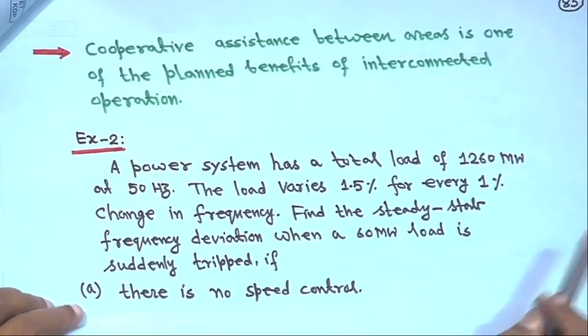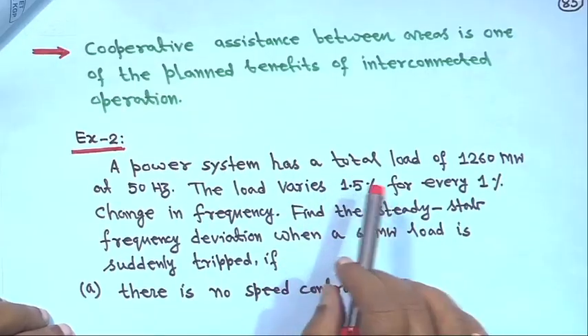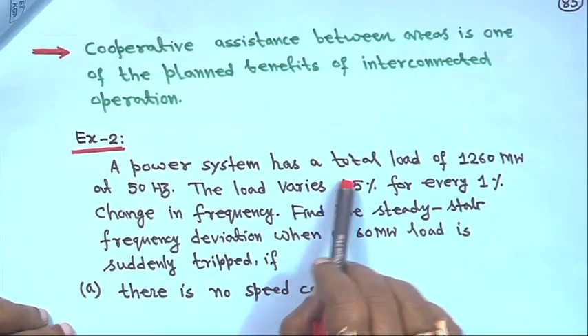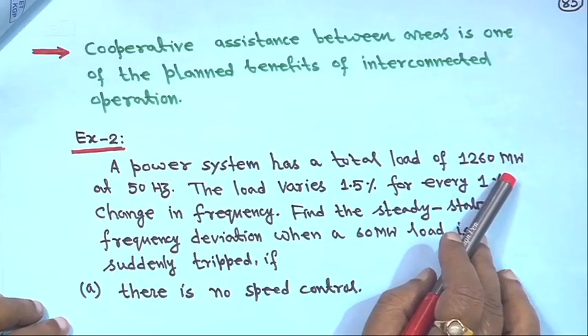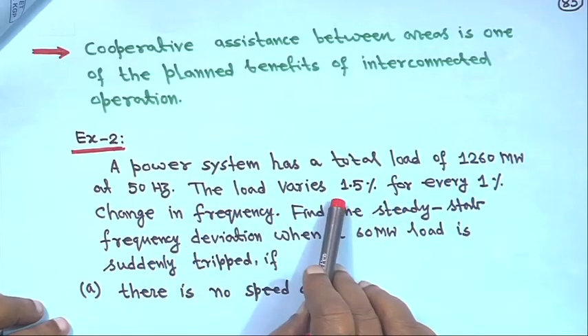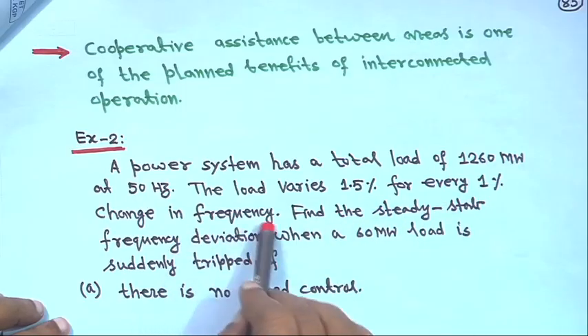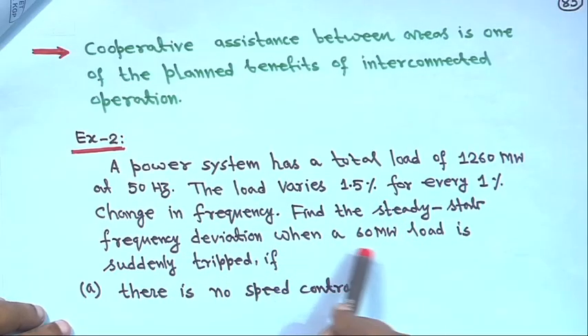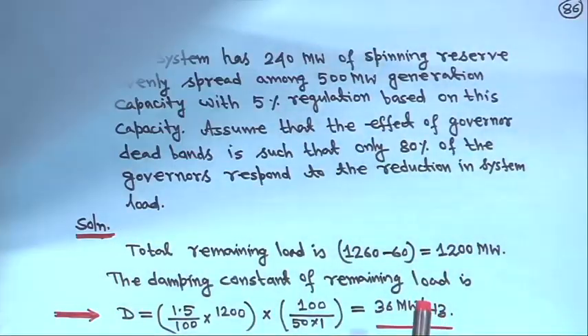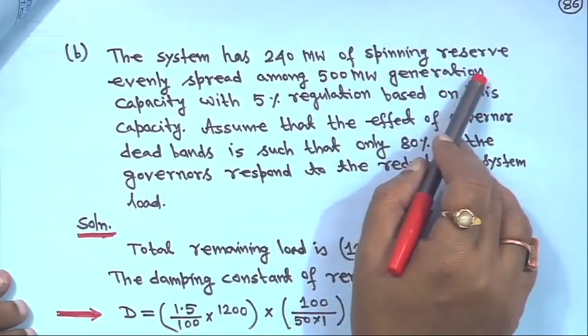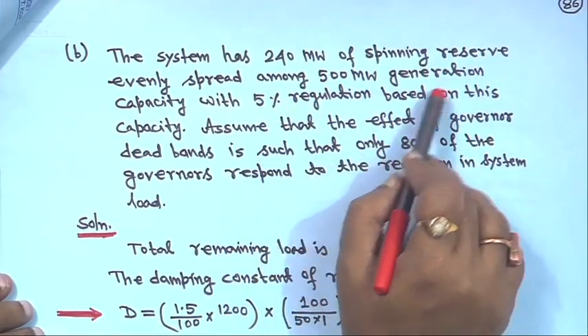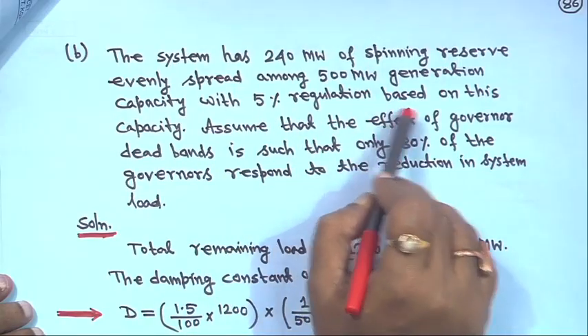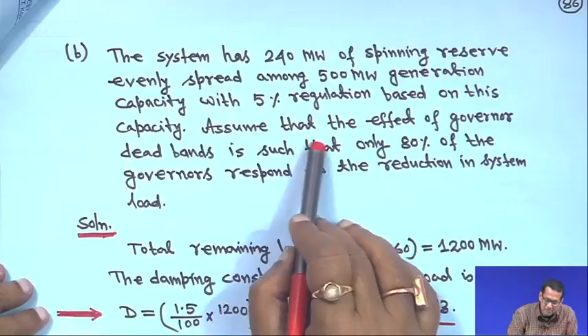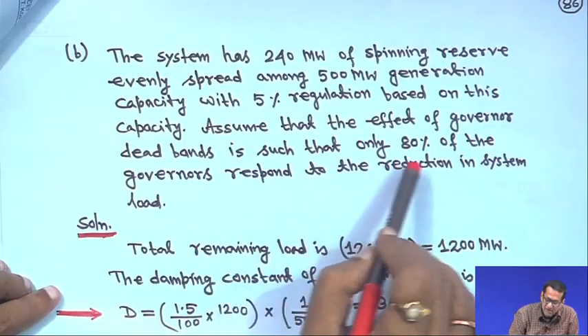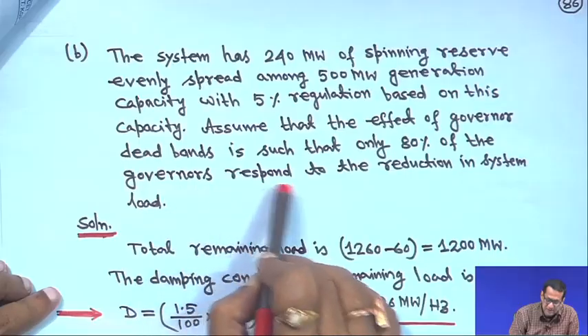Now we will take an example. We will come again to two area modeling and other things, but first look at this example. A power system has a total load of 1260 megawatt at 50 hertz. The load varies 1.5% for every 1% change in frequency. Find the steady state frequency deviation when a 60 megawatt load is suddenly tripped. Number one, if there is no speed control. And second, the system has 240 megawatt of spinning reserve evenly spread among 500 megawatt generation capacity with 5% regulation based on this capacity, right?